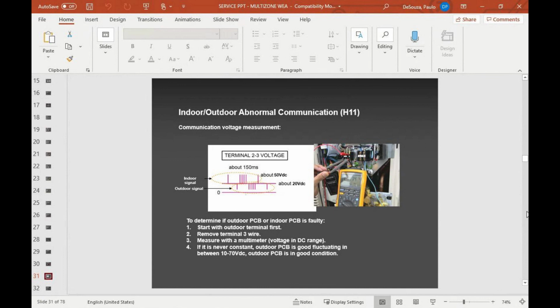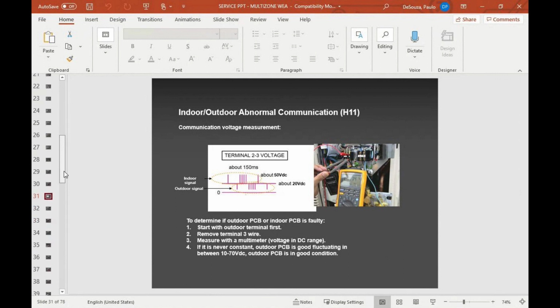Those are the step-by-step, shows you how to see where the problem is. If the problem is outside or if the problem is inside. So basically what it's telling you to do there, on the number 3 wire outside, remove the number 3 wire, turn the power on, if the power is off obviously, turn the power on, and then take your multimeter. Take your multimeter as shown on this drawing here, and put one prong on number 2 and the other one on number 3, and leave the wire hanging.